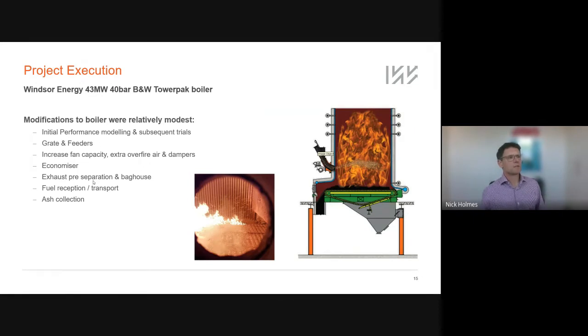So in terms of what had to be done to modify a boiler, the boiler was a Towerpak boiler, similar to the previous one, the Red Stag. So the actual boiler pressure parts themselves were very similar. We initially carried out performance modeling just to understand what needed to be done. Quite a different fuel, quite different combustion characteristics. And it did show that if we just did a straight fuel swap, you'd probably only get about 80% out of that boiler compared to its nameplate rating. So there were quite a few aspects that needed to be addressed.